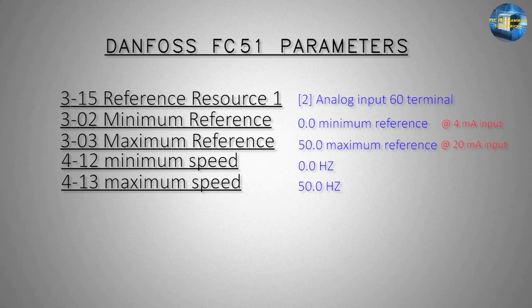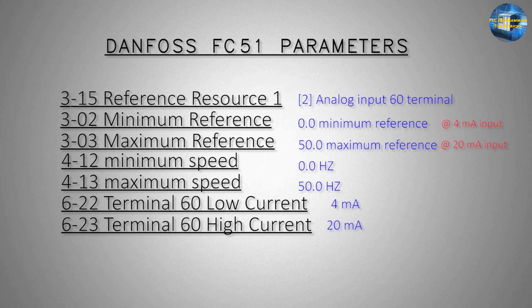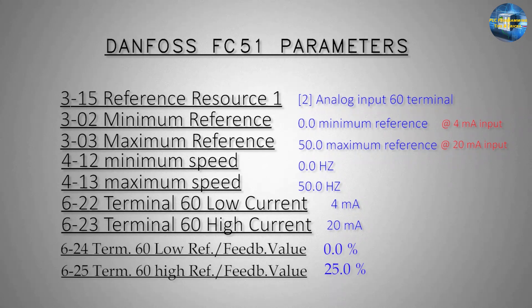Next we can limit the maximum and minimum speed of the motor using parameters 4-12 and 4-13. We can also set the minimum and maximum limits of the analog signal as 4 mA to 20 mA by setting parameters 6-22 and 6-23. Next we have to set parameter 6-24 low reference as 0.0 and maximum reference 6-25 as 25.0. These two parameters are a little tricky, so adjust them carefully — they are used to scale the reference input analog signal.